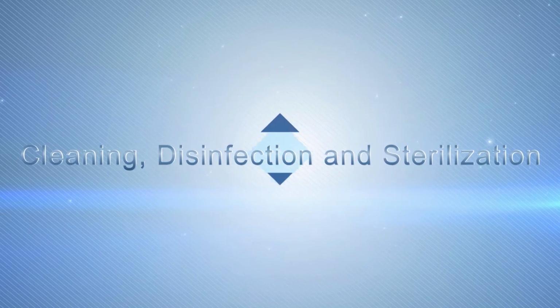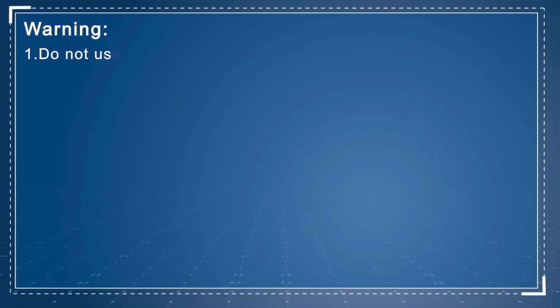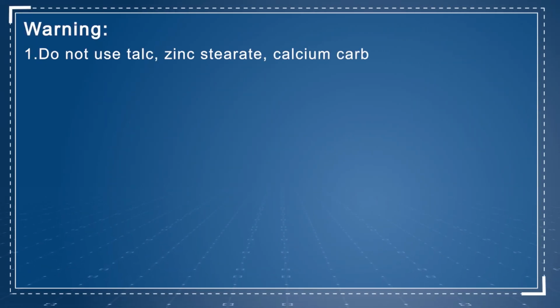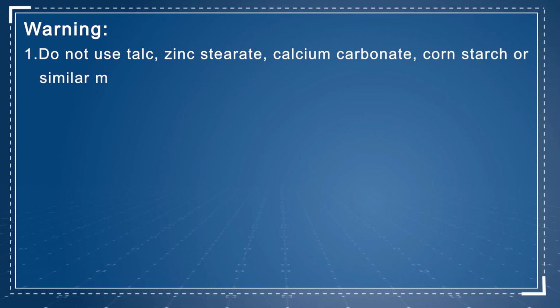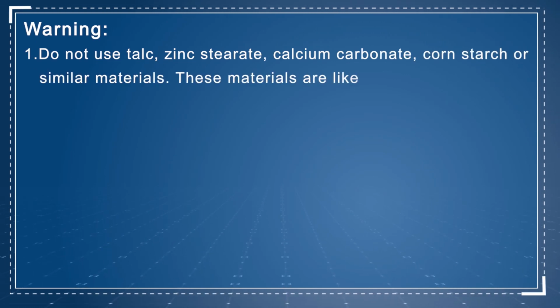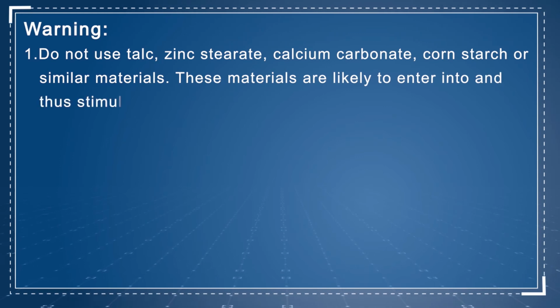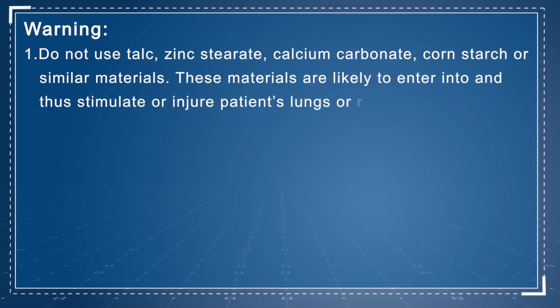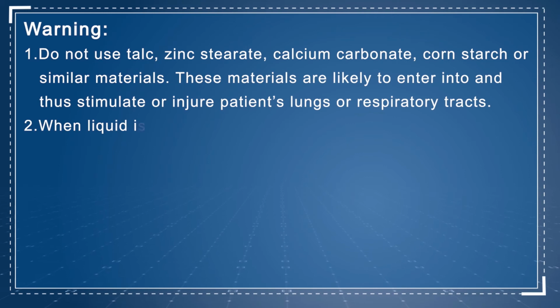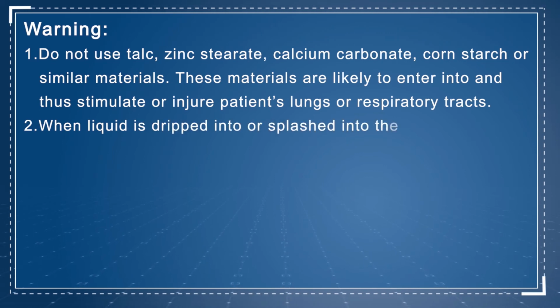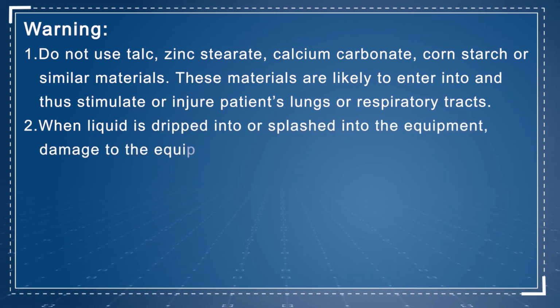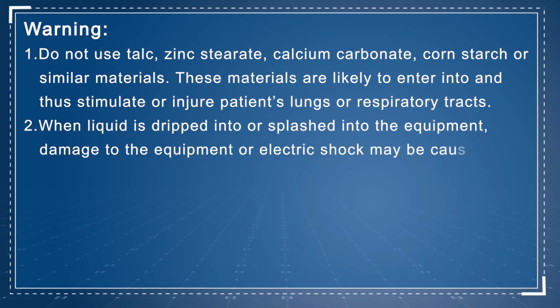Cleaning, disinfection, and sterilization. Warning: 1. Do not use talc, zinc stearate, calcium carbonate, cornstarch, or similar materials. These materials are likely to enter and thus stimulate or injure the patient's lungs or respiratory tract. 2. If liquid is dropped or splashed into the equipment, damage to the equipment or electric shock may be caused.